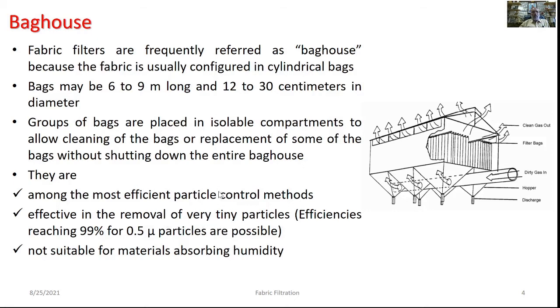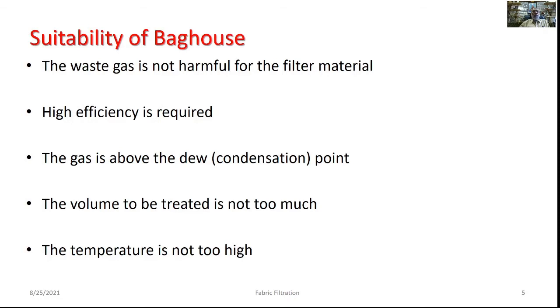Baghouses have certain limitations: they are not suitable for materials absorbing humidity. A baghouse is suitable where the waste gas is not harmful to the filter material, where high efficiency is required, the gas is above its dew point, the volume to be treated is not too large, and the flue gas temperature is within a range that will not affect the filter material.